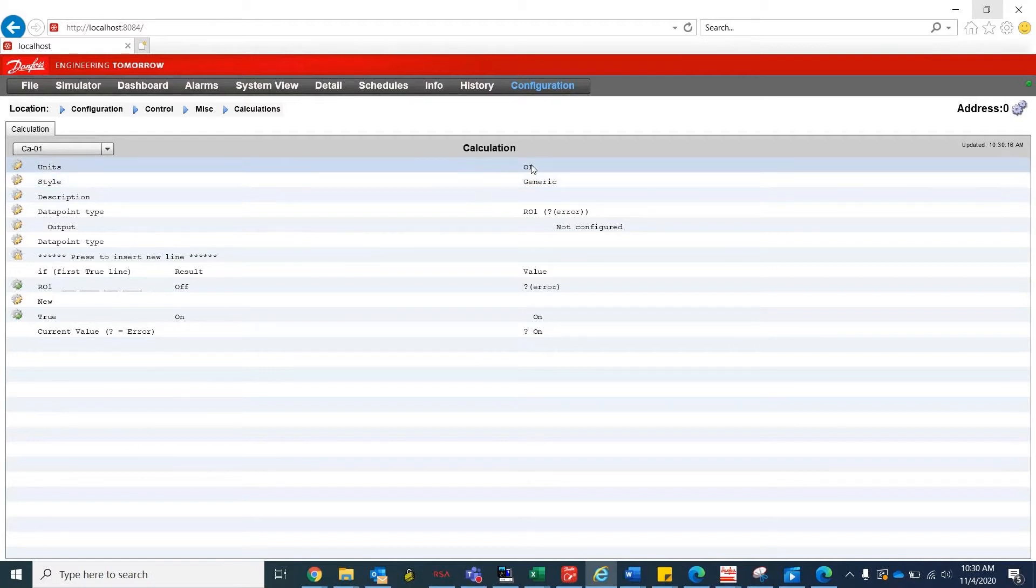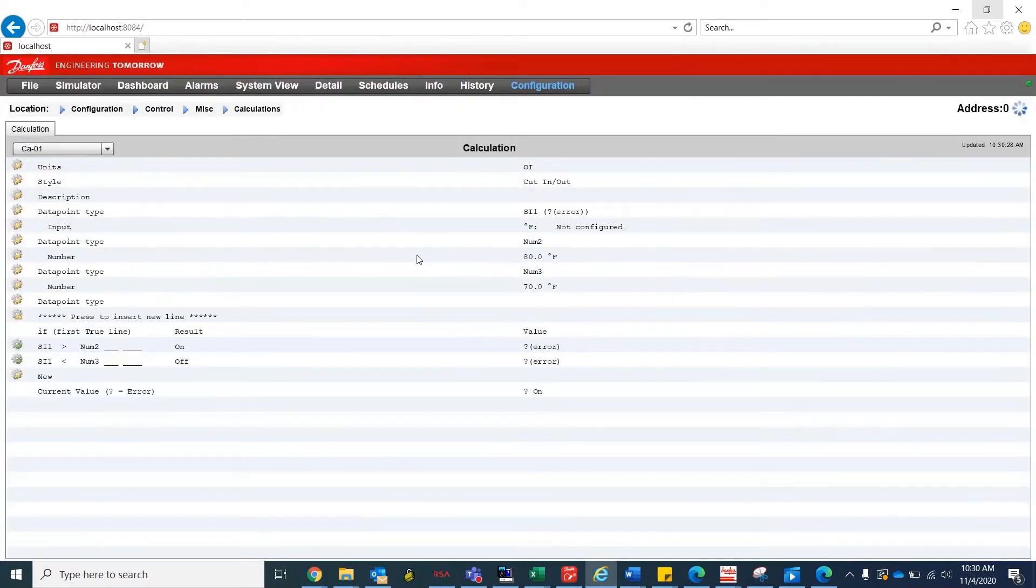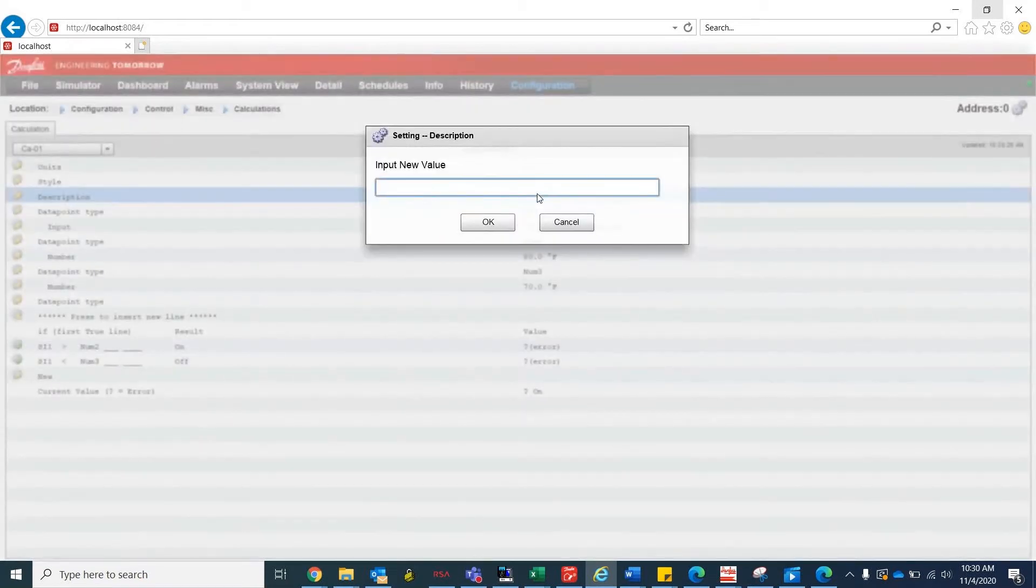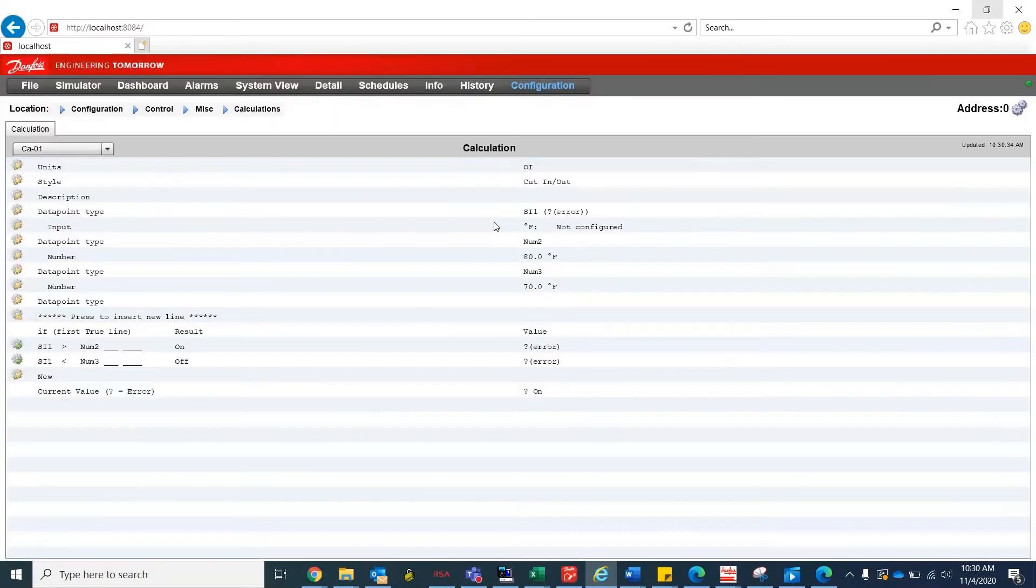For units, we'll be selecting OI, the digital signal, and for style, we'll be selecting cut-in slash cut-out. Description is where we add the title for the calculation. So for this example, we'll be writing exhaust fan in. The SI1, which stands for sensor input 1, will be choosing the compressor sensor.